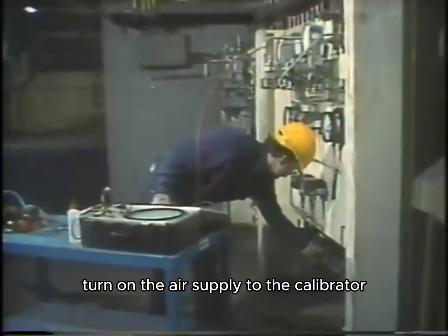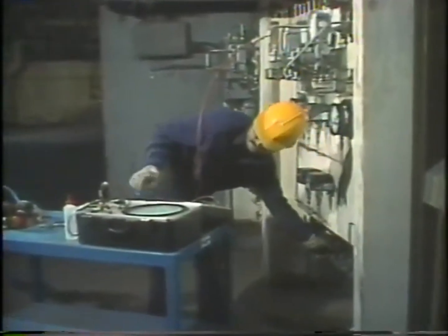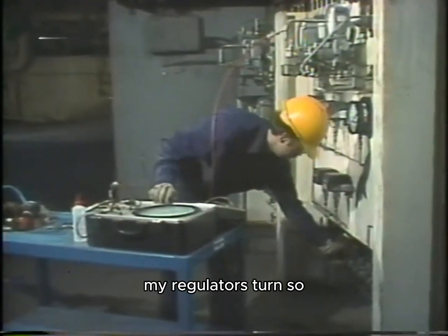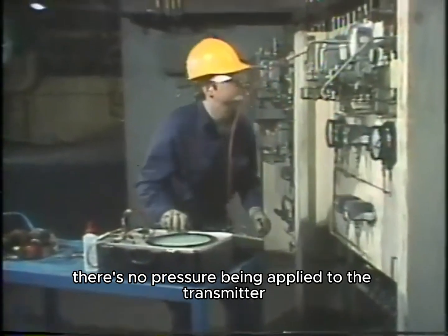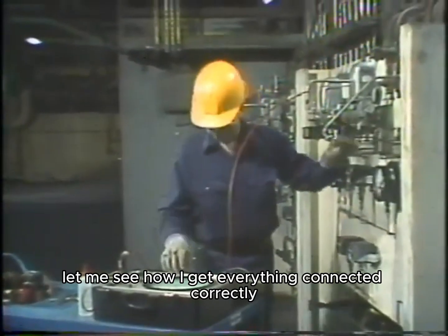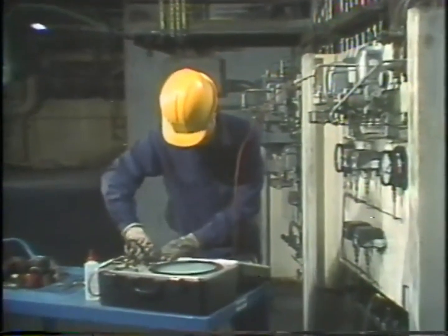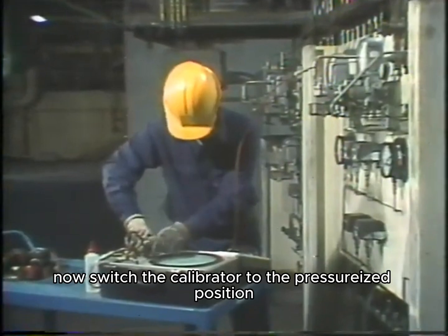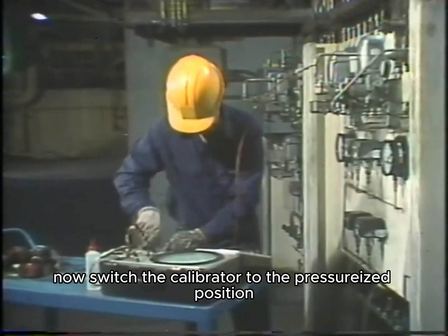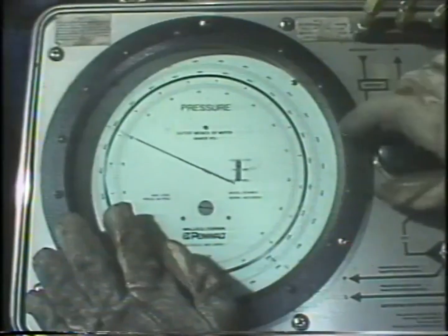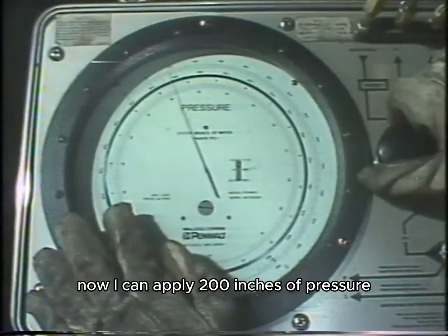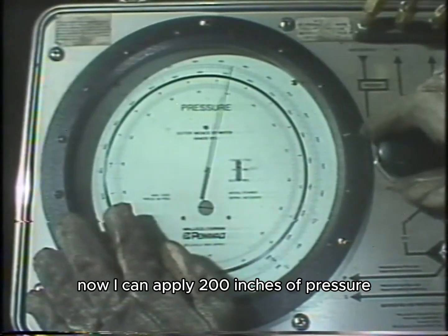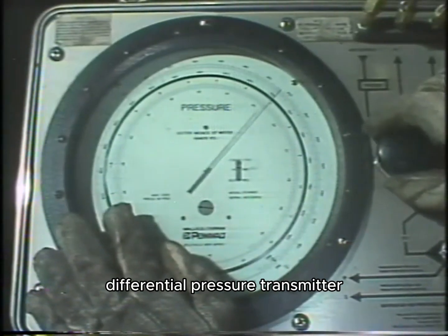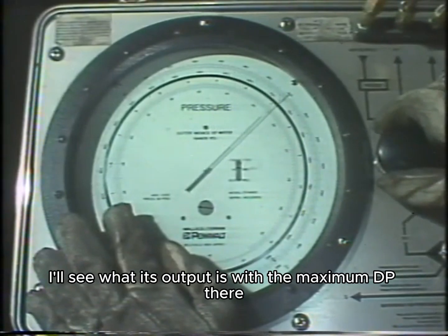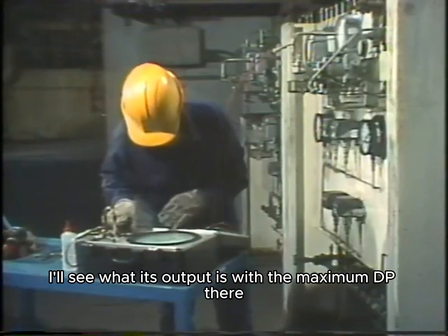Turn on the air supply to the calibrator. And my regulator's turned so there's no pressure being applied to the transmitter. Let me see, I've got everything connected correctly. Now I'll switch the calibrator to the pressurized position. Now I can apply 200 inches of pressure to the high side of the differential pressure transmitter. I'll see what its output is with a maximum DP. There.